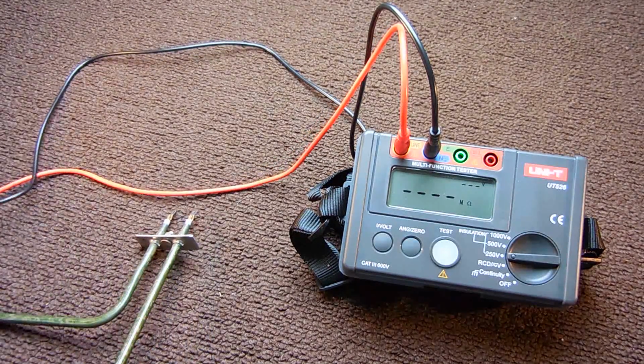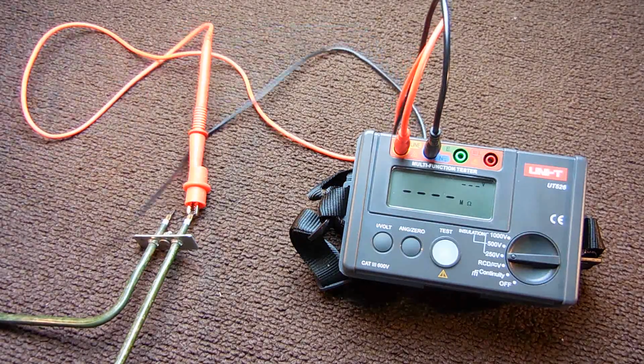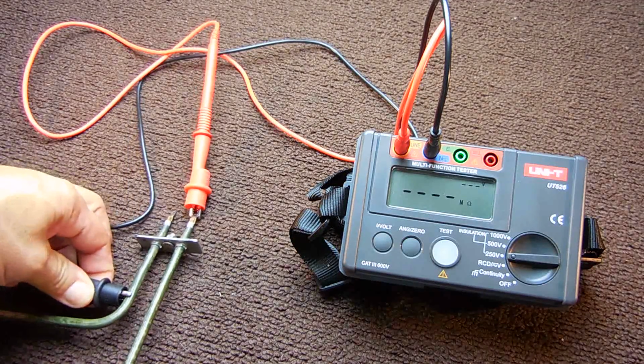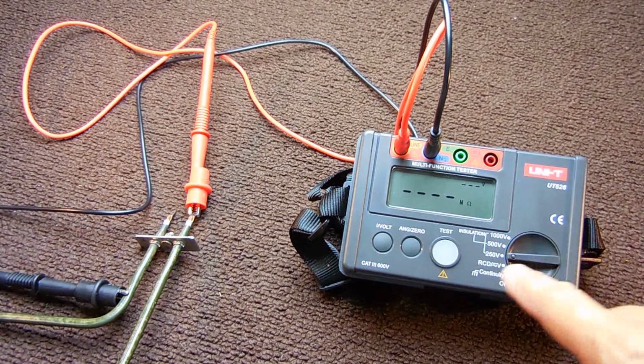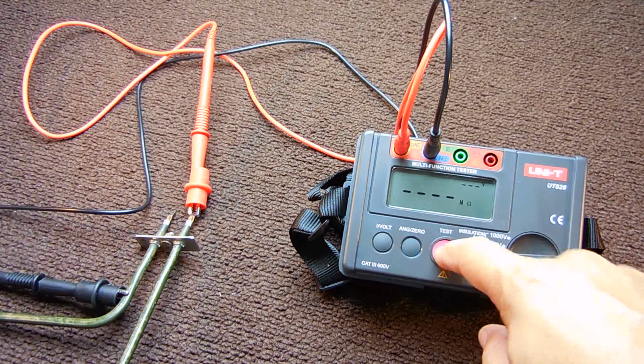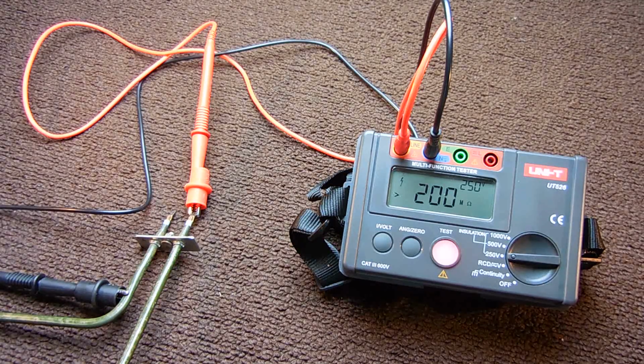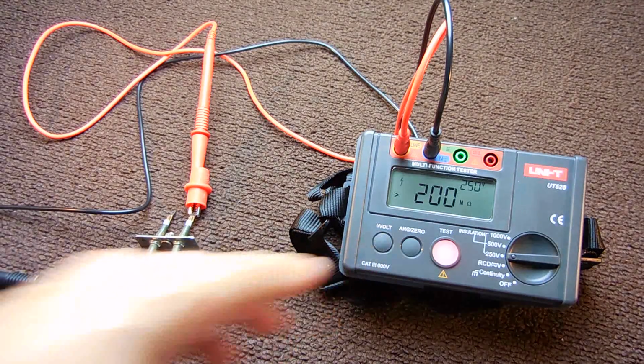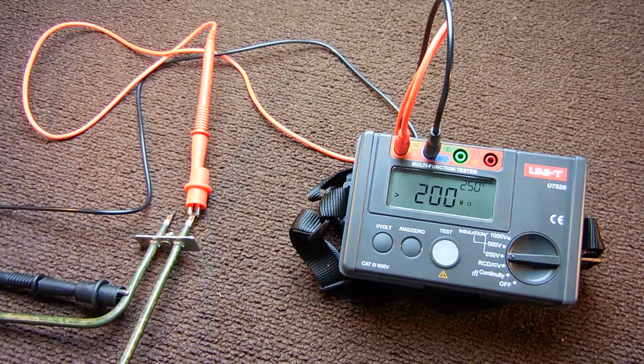Now let's take a look at the heating element. Take one lead, connect it to the terminal here, and we're going to take the other and connect it right on here. Then we're going to push the button right here, 250 volts. This is a 120 volt element. And you can see the test shows it's over 200 megohm. If you see an element that's down around 2 megohm or less, it's getting very close to fail, and you should definitely replace that element.